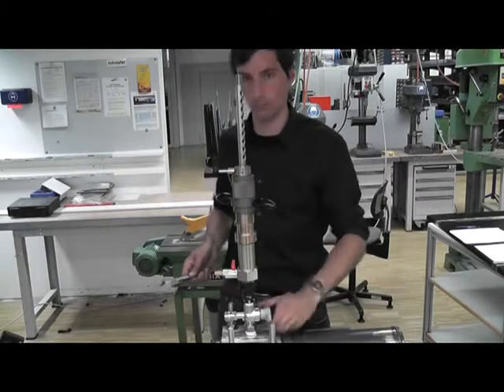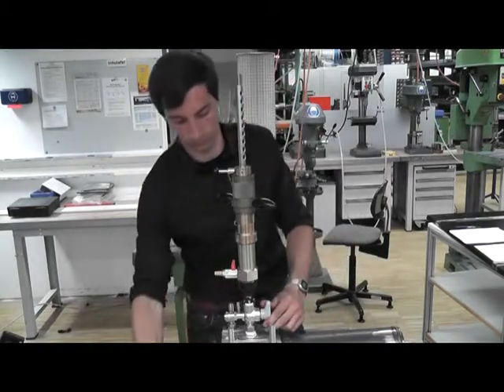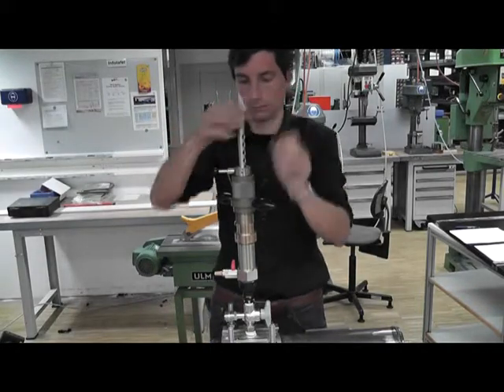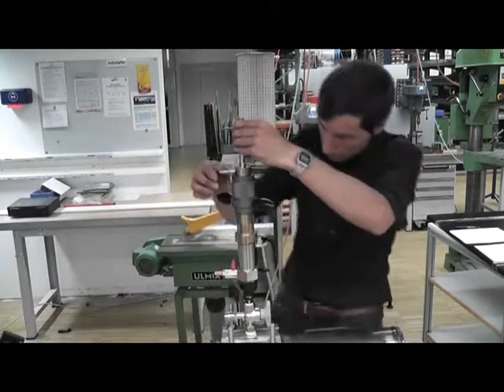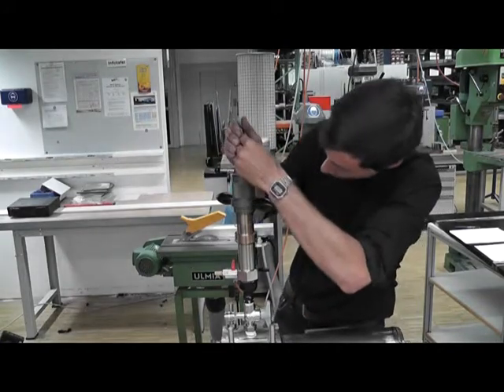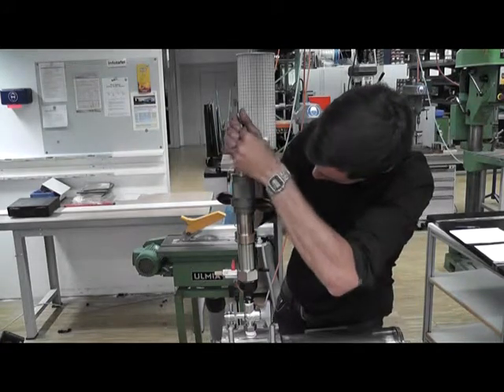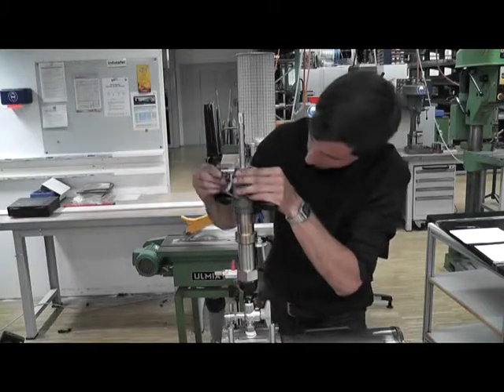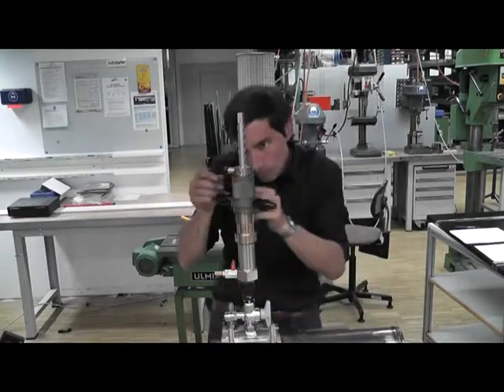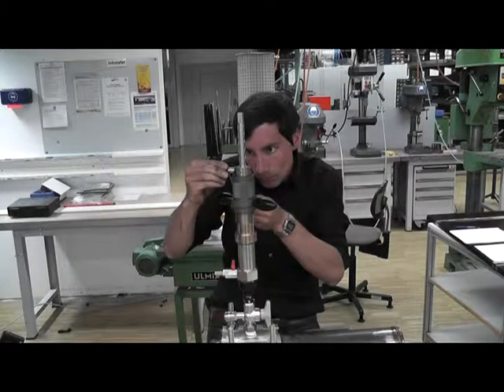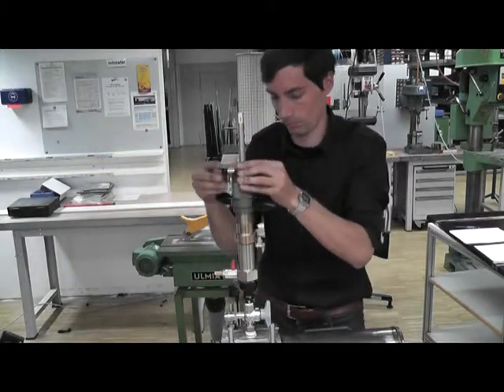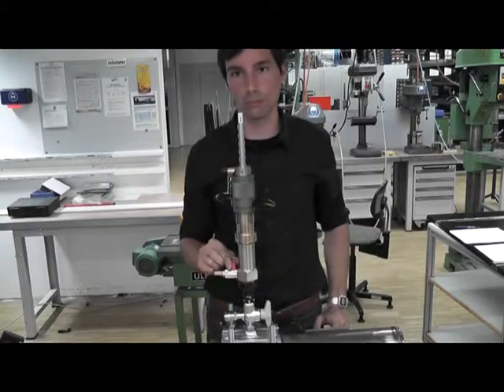For drilling, the ball valve has to be opened. Now press the driller down till the outer wall of the pipe. Before drilling, the most important point is to mount the security bolt plus the security ring. The last point is to open the valve on the driller. If this valve is opened, all swarf of the drilling will be caught inside the filter and no swarf will be inside the pipe.